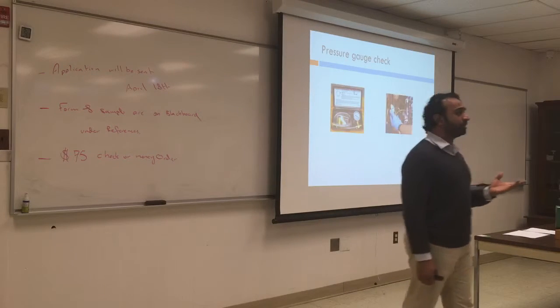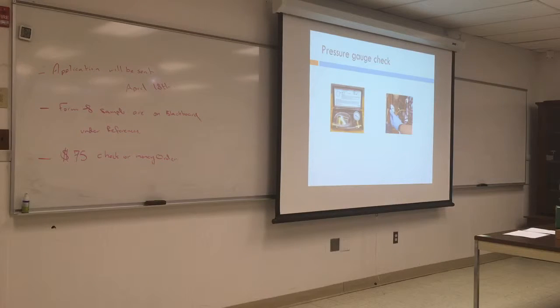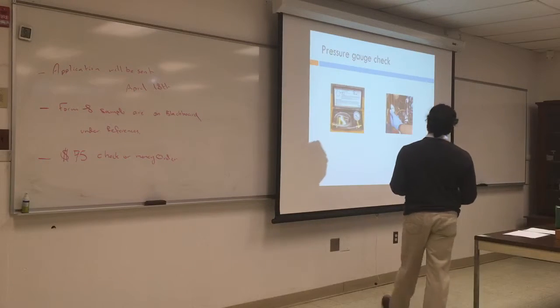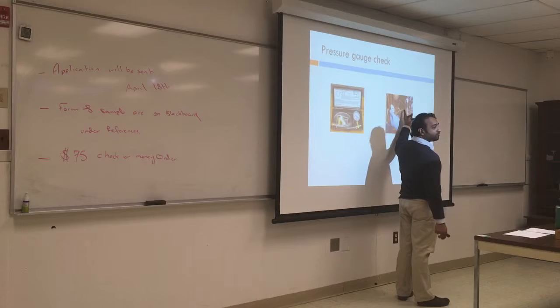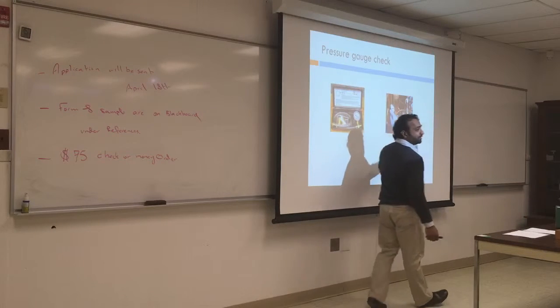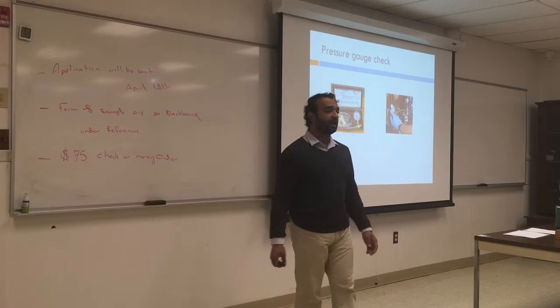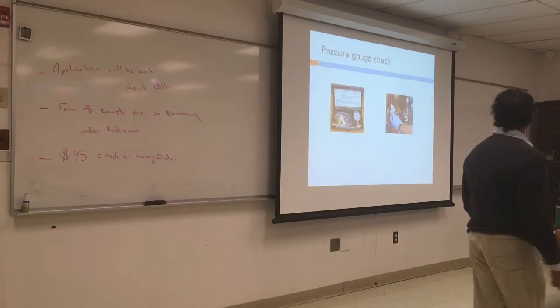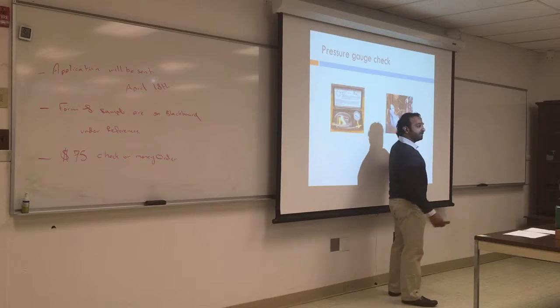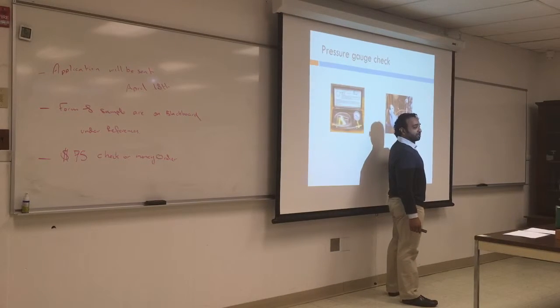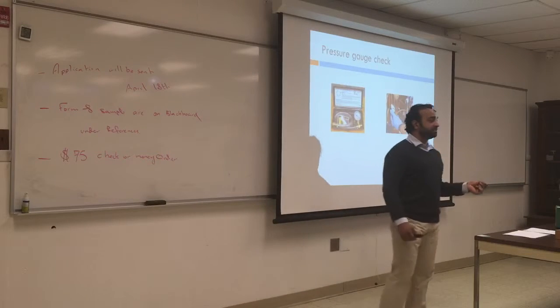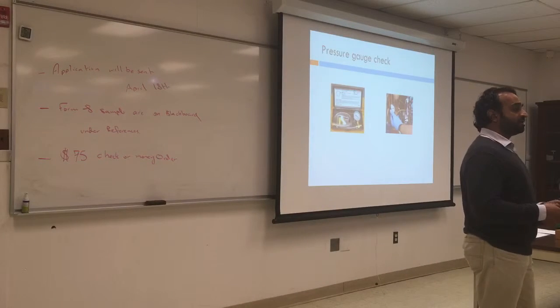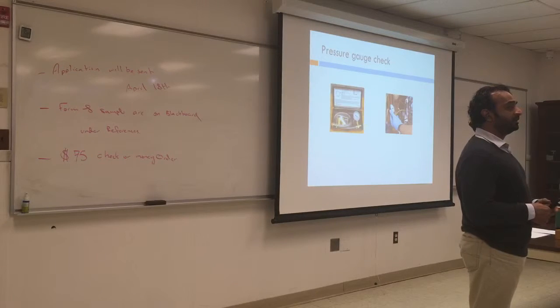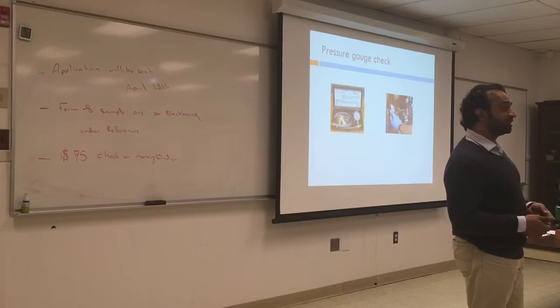So we stopped for spring break at the pressure check. That's something you need to do when you do preventive maintenance. You want to make sure that the pressure is set at the right pressure. So you install your gauge at the outlet of the pump and check the pressure. Don't just guess, look at the tag. The tag should tell you that the pressure should be set at 100, 120, or 150, and you set it at that pressure. Then you turn off the equipment, and the pressure should drop by 10 to 15% and stop dropping. If it keeps dropping, it means there's a leak in the system.